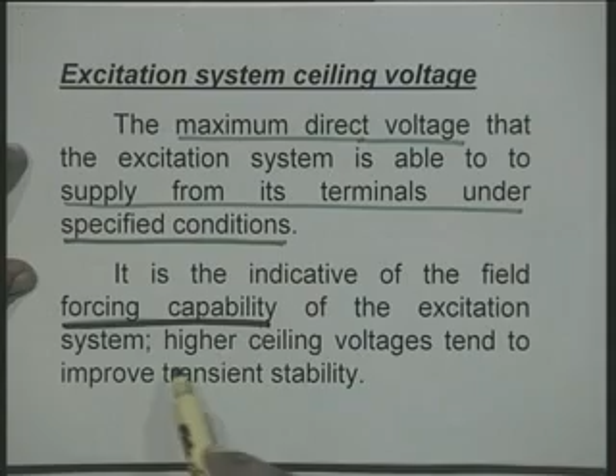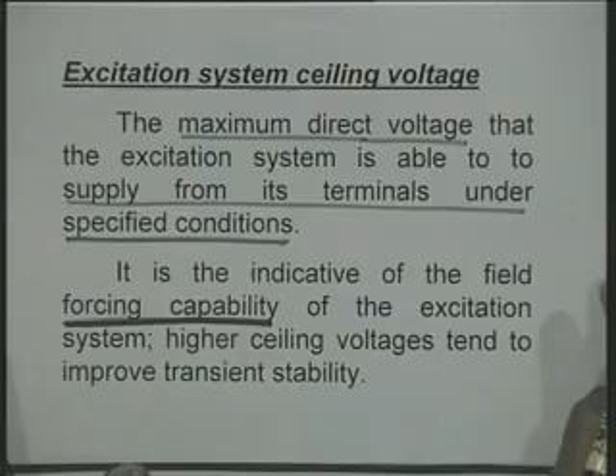Now, related to the dynamic performance measures, there are some basic definitions we have to clearly understand. The excitation system ceiling voltage is the maximum direct voltage that the excitation system is able to supply from its terminals under specified conditions. It is indicative of the field forcing capability of the excitation system. Higher ceiling voltages tend to improve transient stability. This is a very important factor: excitation systems which have higher ceiling voltages will have higher field forcing capability, and the resulting transient stability limit will be high.